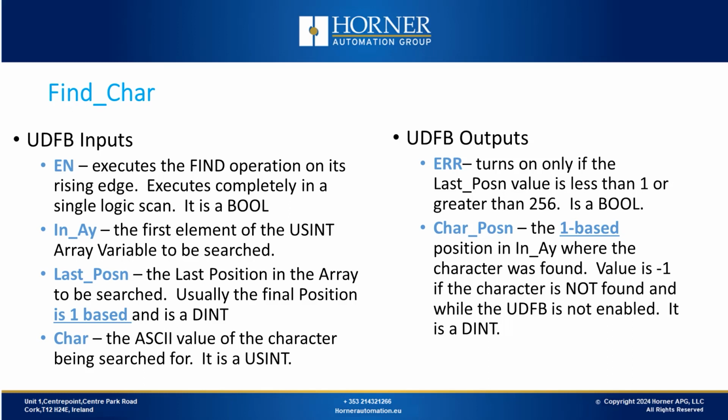We will also look at the specific inputs and outputs for the find character UDFB. Once again, we will use this function to search through an array of characters or an array of unsigned short integers, which is how standard IEC and Cscape handle strings. This UDFB has four inputs. Similar to the previous UDFBs we looked at, this UDFB also has an enable input. This input only executes on the leading edge.